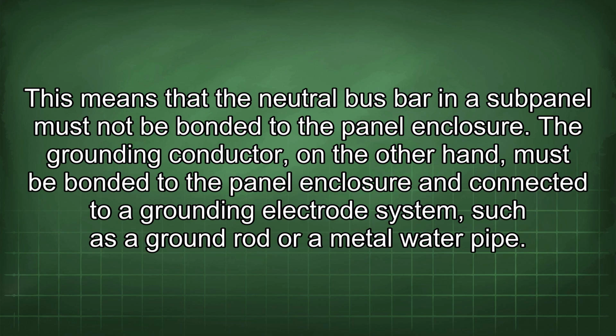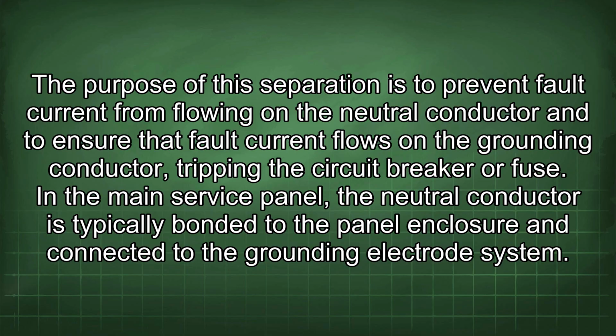The grounding conductor, on the other hand, must be bonded to the panel enclosure and connected to a grounding electrode system such as a ground rod or a metal water pipe. The purpose of this separation is to prevent fault current from flowing on the neutral conductor and to ensure that fault current flows on the grounding conductor, tripping the circuit breaker or fuse.